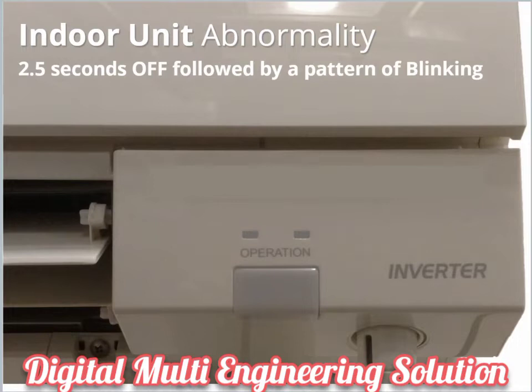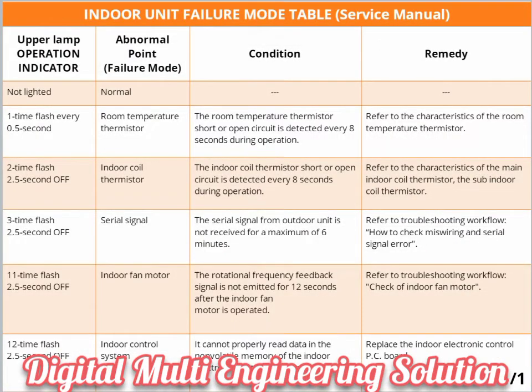The number of blinks and beeps indicates a unique error. Record the number of blinks and reference the indoor unit failure mode table in the service manual. It's important to note that the blinking patterns for Failure Mode Recall differ from the ones of the Troubleshooting check table. Pause the playback here to review all of the abnormal points.